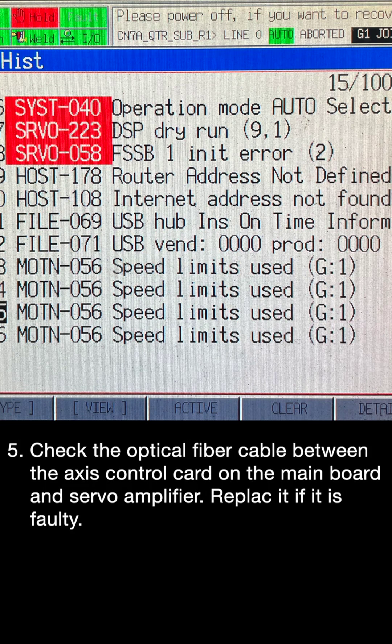Step 5: Check the optical fiber cable between the axis control card on the main board and the servo amplifier. Replace it if it is faulty.